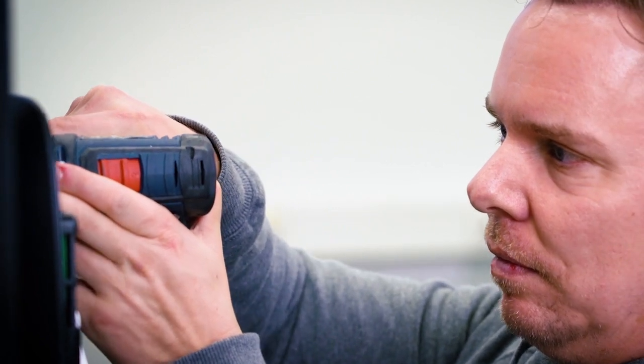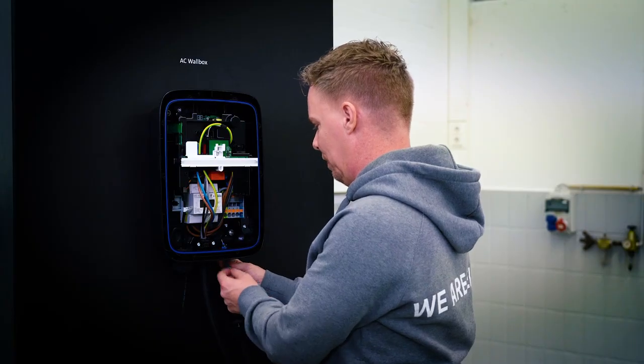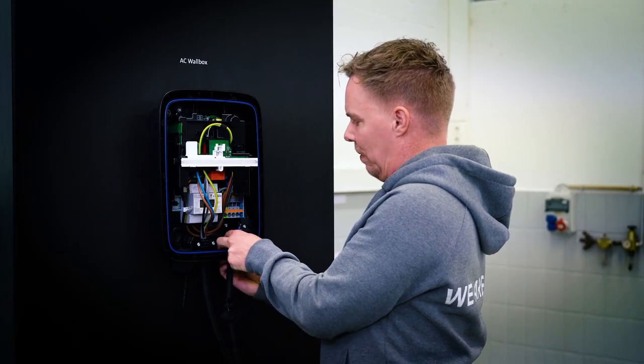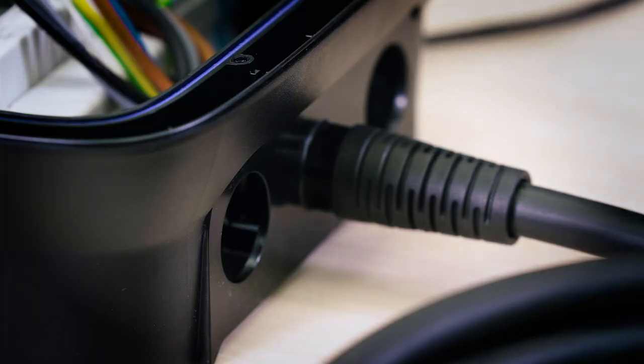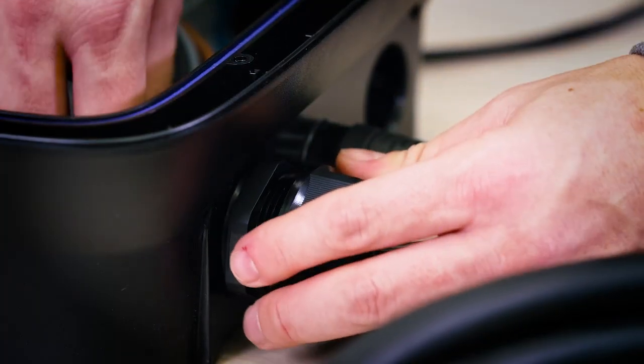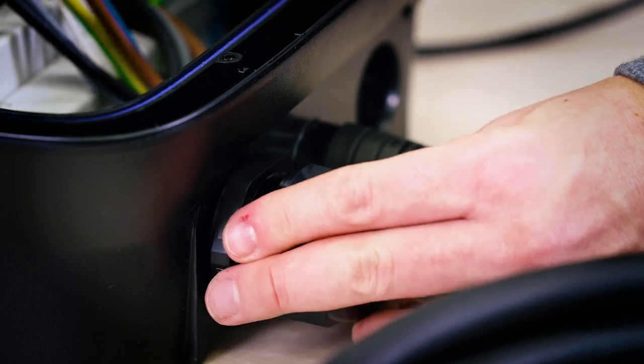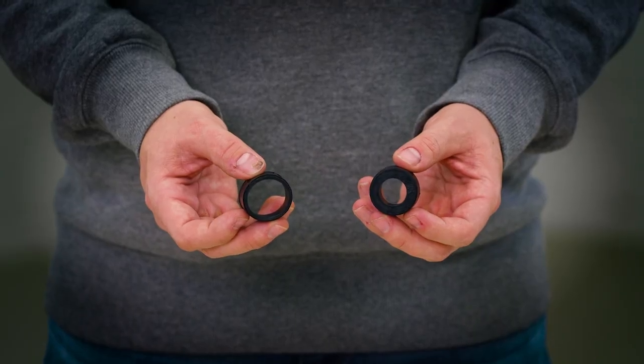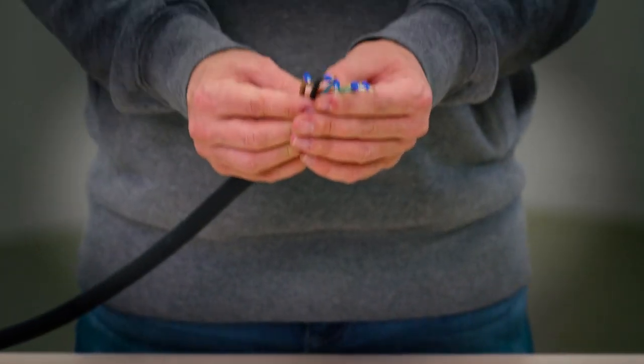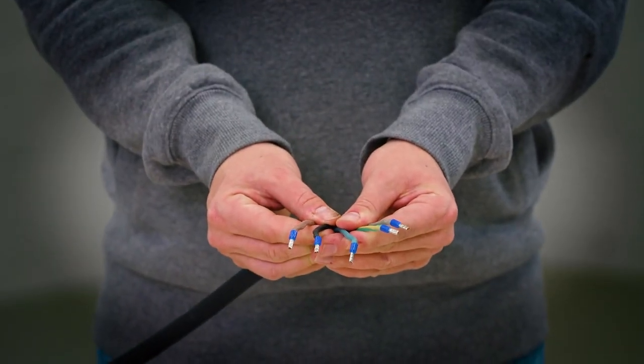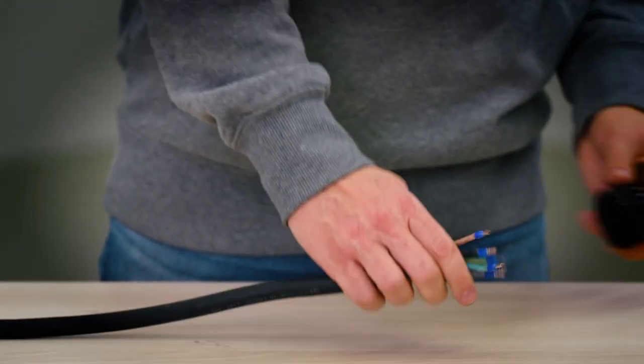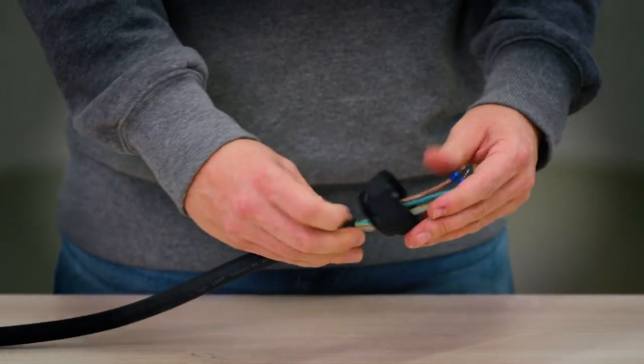Tighten the screws. If you are feeding the cable from the bottom, feed it through the cable gland on the bottom. You can also feed an Ethernet cable through the slotted seal kit of the cable gland here. Select the seal ring in accordance with the cable diameter. To connect the infrastructure cable, use either stranded wire or solid conductors. Strip the wires to a length of 10 to 12 millimeters. For 22 kilowatts Elli Charger 2 models, strip 18 to 20 millimeters of insulation.